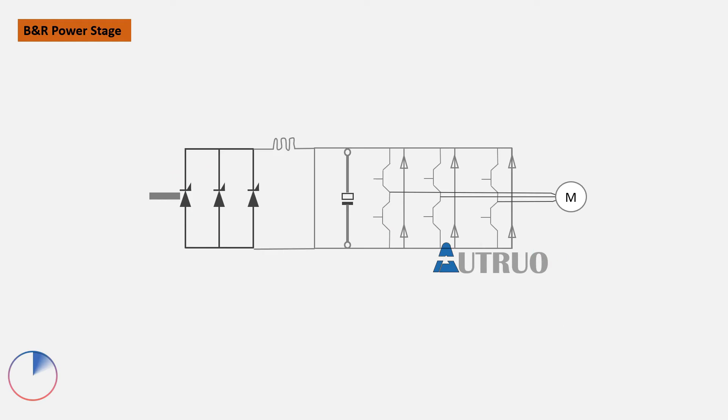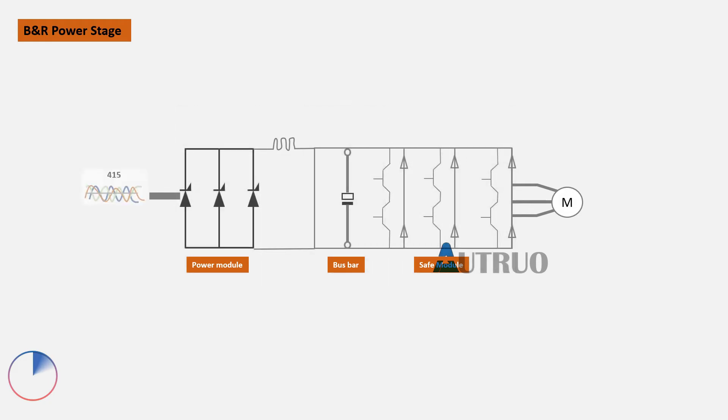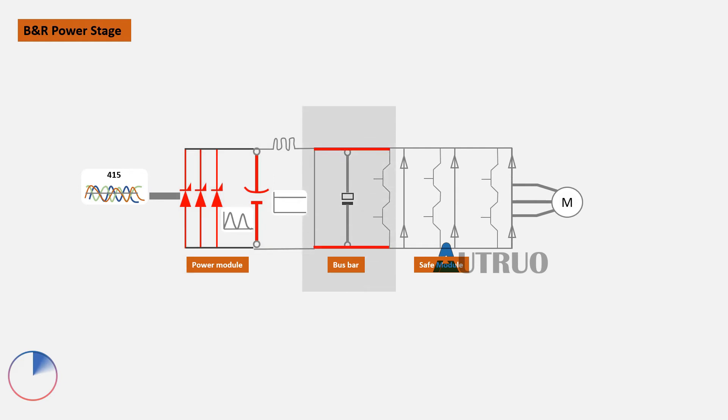The first circuit in the ACOPOS multi system is the power module, followed by the bus bar, and finally the safe motion modules. The power modules convert the incoming 415V AC to DC through the use of diodes and other electronic components. After conversion, the converted voltage is fed to the bus bar, from which the safe motion drives are powered.